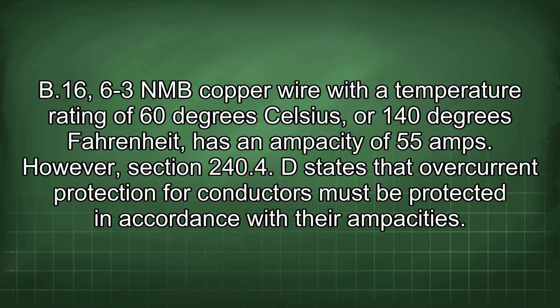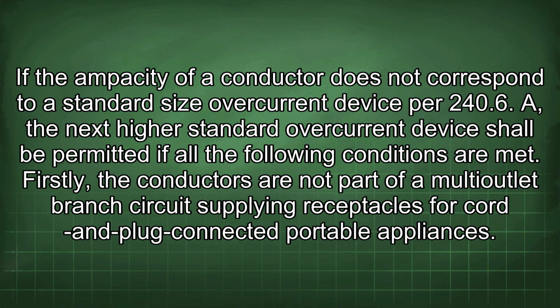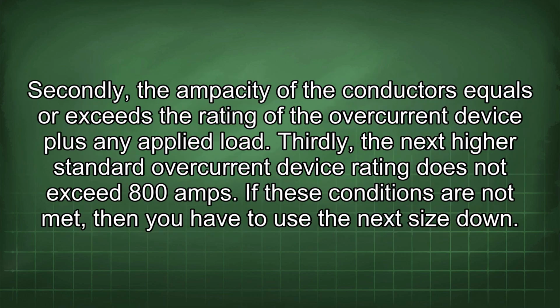However, Section 240.4(D) states that overcurrent protection for conductors must be in accordance with their ampacities. If the ampacity of a conductor does not correspond to a standard size overcurrent device per 240.6(A), the next higher standard overcurrent device shall be permitted if all the following conditions are met. Firstly, the conductors are not parts of a multi-outlet branch circuit supplying receptacles for cord and plug connected portable appliances. Secondly, the ampacity of the conductors equals or exceeds the rating of the overcurrent device plus any applied load. Thirdly, the next higher standard overcurrent device rating does not exceed 800 amps. If these conditions are not met, then you have to use the next size down.